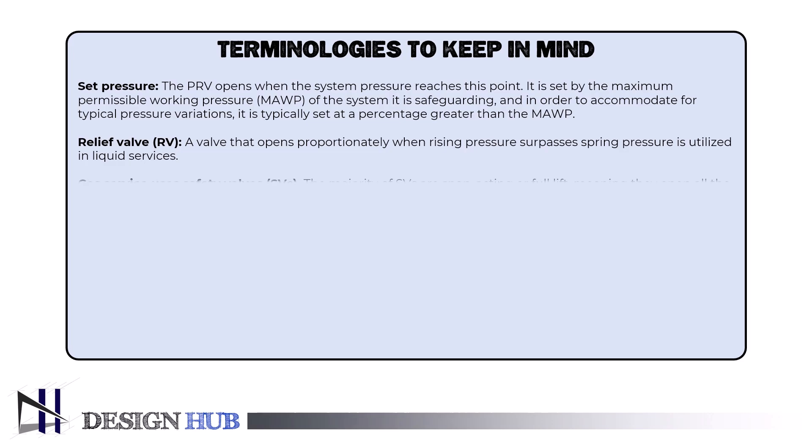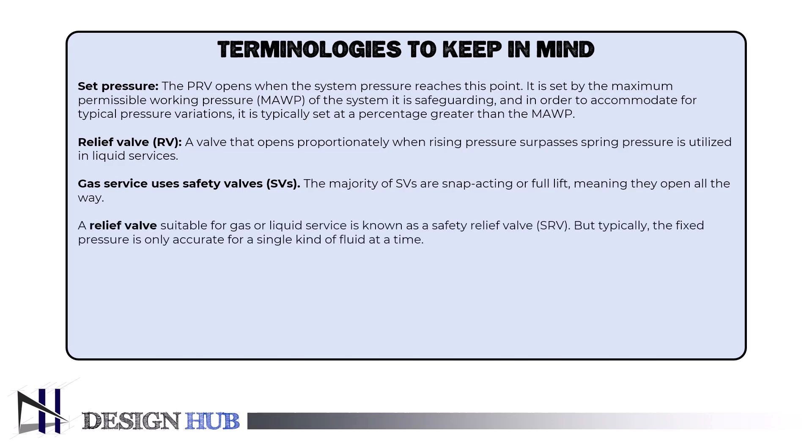The third is safety valves, SVs: used in gas service, with the majority being snap acting or full lift, meaning they open all the way. The fourth is a safety relief valve, SRV: suitable for gas or liquid service, but typically the fixed pressure is only accurate for a single kind of fluid at a time. Fifth is pilot-operated relief valves: relief valves activated remotely from a pilot valve attached to the system pressure upstream.